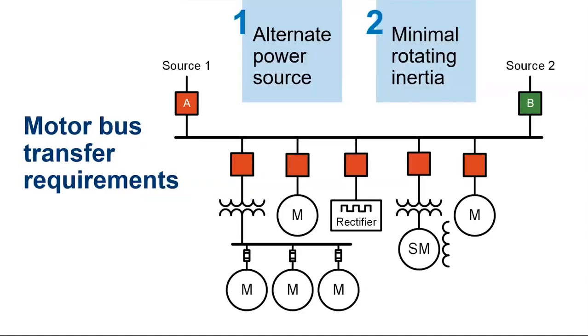To implement a motor bus transfer scheme, consider that transfer success improves as the inertia and capacitance on the system increase. A successful transfer is greatly dependent on the characteristics of the load, which is the inertia of the load. There are two requirements for motor bus transfer. First, definitely having an alternate power source where the load can be transferred to. The second is minimal rotating inertia that supports the load while the bus is being transferred to the alternate source.